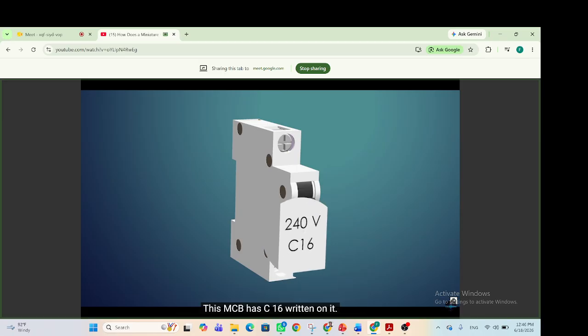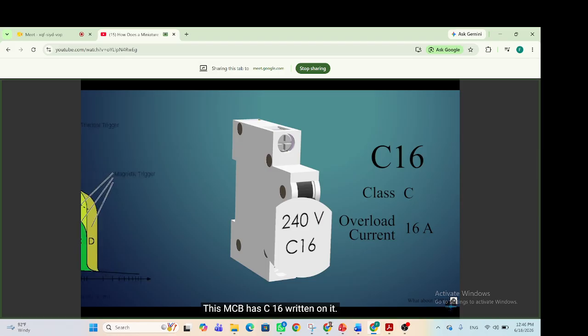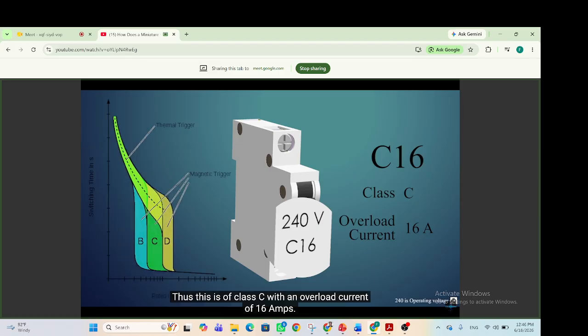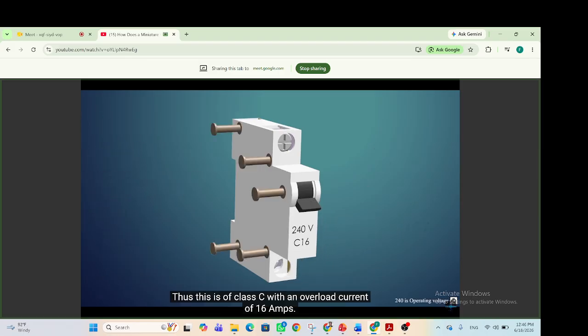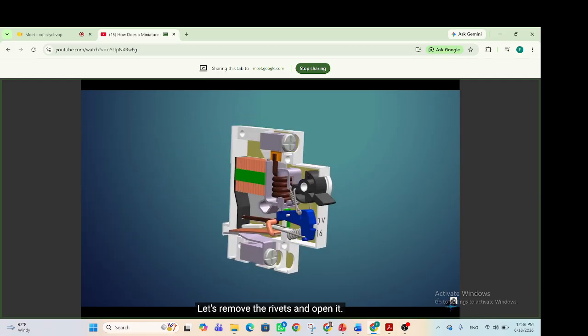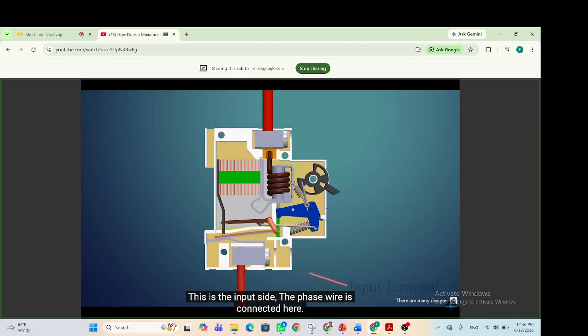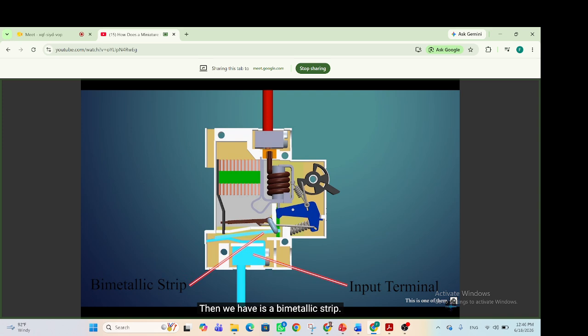This MCB has C16 written on it. Thus this is of class C with an overload current of 16 amps. Let's remove the rivets and open it. This is the input side. The phase wire is connected here. Then we have a bimetallic strip.